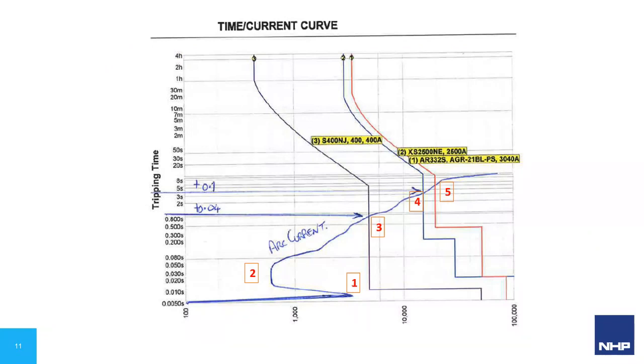For those who haven't seen this sort of graph before, there's a very good webinar on selectivity that was carried out on this same NHP channel a couple of weeks ago. And this is the time current curve, with time going up the left-hand side and current going along the bottom, and both are logarithmic scales. These three curves represent a small molded case breaker on the left, going up to a larger molded case breaker, up to an ACB. The idea is that if you get a fault downstream of all three, then the smallest breaker will trip first. If it's upstream of that, then the next one, then the next one. You can see the ACB is designed to sit on a fault for a significant amount of time, so that with a downstream fault, your main incoming circuit breaker doesn't trip out.